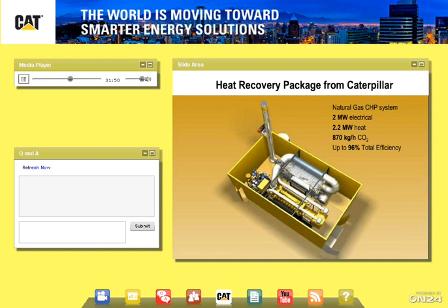Now, here we can take a look at what a typical cogeneration system might look like. Under these circumstances, the module on the front of that engine is the jacket water heat exchanger. That's sized for taking the heat out of that engine and using it. You only need to use that if that's all you need for hot water. You may want to use the exhaust system as well and take the heat out of there. So the device sitting next to the engine in this case is a combined muffler, heat exchanger, and exhaust after-treatment system, all tied together in one module.